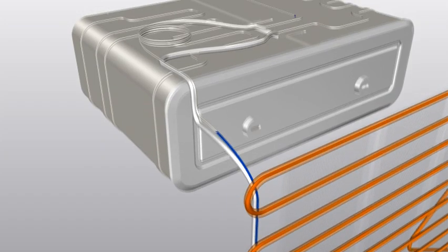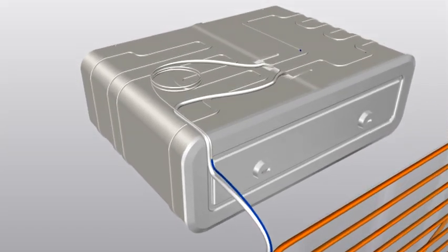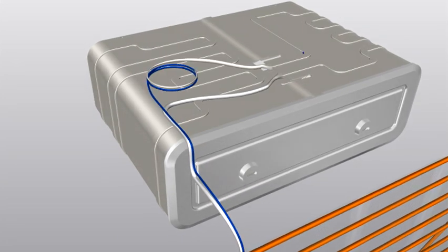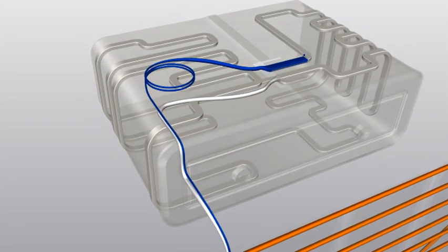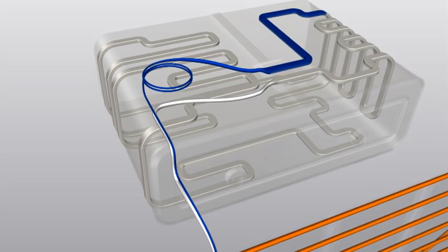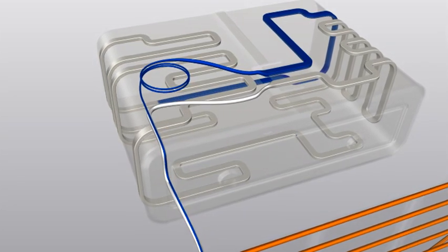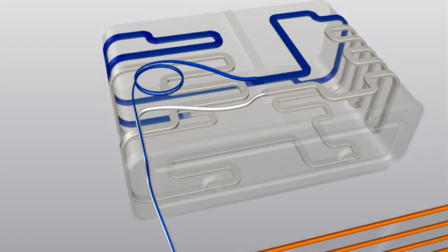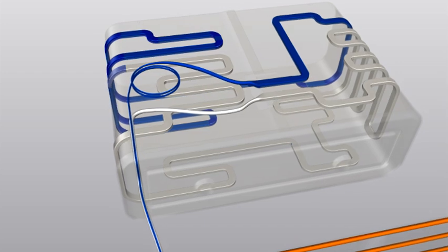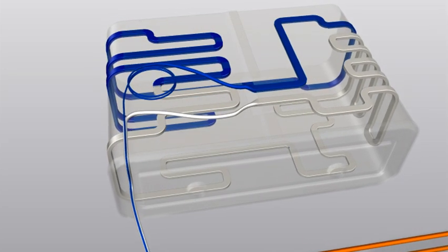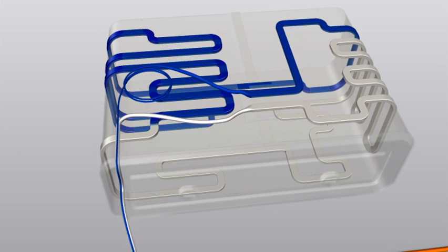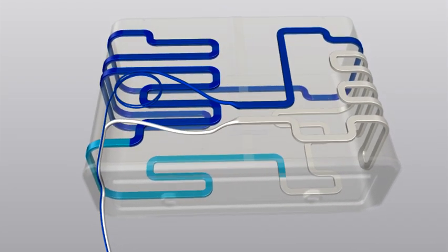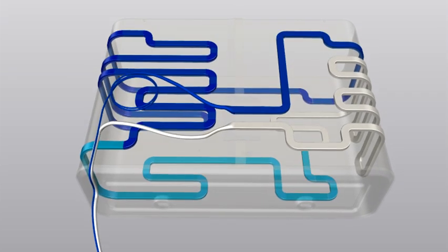Subcooled and low-pressure liquid refrigerant enters the evaporator, where it suddenly expands and its pressure further decreases. The refrigerant temperature is automatically lowered. The mixture of vapor and liquid refrigerant passes through the evaporator coils. The liquid refrigerant evaporates in the evaporator coil. The latent heat needed for evaporation is absorbed from the refrigerator cabinet.